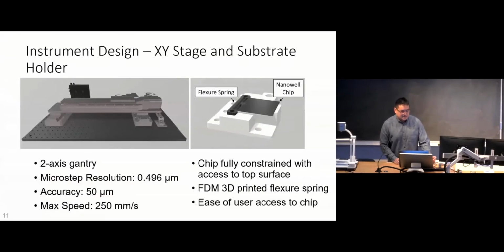Next, we have a 2-axis gantry system for positioning our substrate below the inkjet nozzle. It is a stepper motor driven linear stage with a microstep resolution of 0.496 micrometers and an accuracy of 50 microns. The high resolution stage allows for accurate positioning of the small features of the nanowell below the nozzle. This stage also has a top speed of 250 millimeters per second, allowing for fast traversal of the nanowell chip during printing. To secure the chip during printing, a custom holder was made using 3D printed parts. The top surface of the chip has to be kept unobstructed in order to make clearance for the nozzle moving above the substrate, and in addition to allow for the application of a microseal after printing.